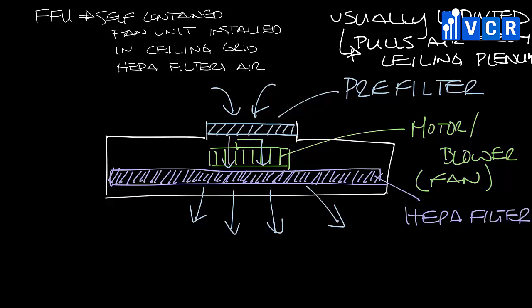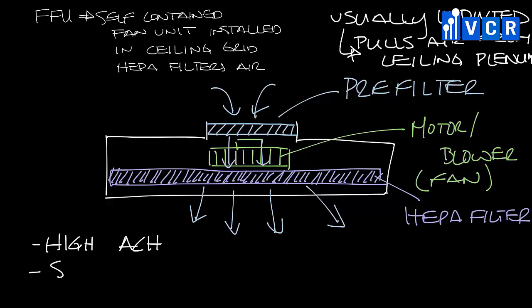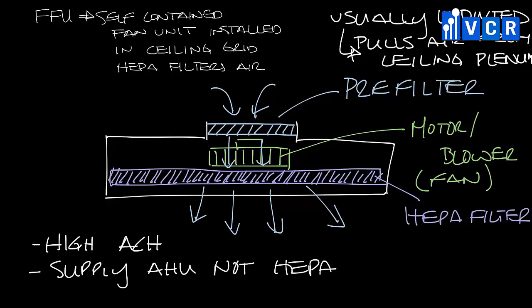You'll often see fan filter units when the room air changes per hour requirement for a space is high, or when the supply air handler isn't HEPA filtered but a certain space needs HEPA filtration.